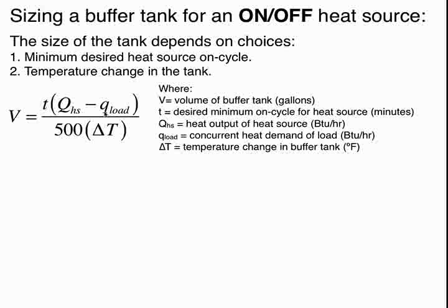Now, some heat sources won't fire, or they won't operate, unless there's some kind of a load calling for heat. It depends on how your system controls are set up. The conservative thing would be to treat Q sub load as 0. Let's assume that there's no simultaneous heating load, that all the heat production from the heat source is going into thermal storage. And then we divide by 500, and we divide by the temperature swing that we are going to allow that buffer tank to go through.